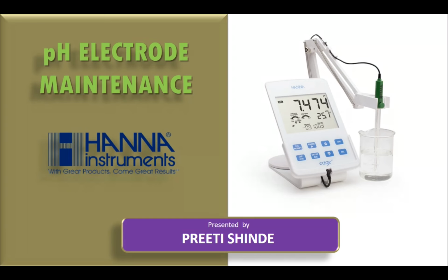One has to dip the electrode in the sample and note down the measurement. But the question arises when the readings are not stable or not accurate or are totally unexpected. Then the question comes: is my electrode working fine, or does my meter have a fault, or is my buffer or my sample wrong? So today we are going to discuss the working of the pH electrode, the cell potential, and what factors affect the working of the pH electrode, and many more facts that users should know before we start using a pH electrode.